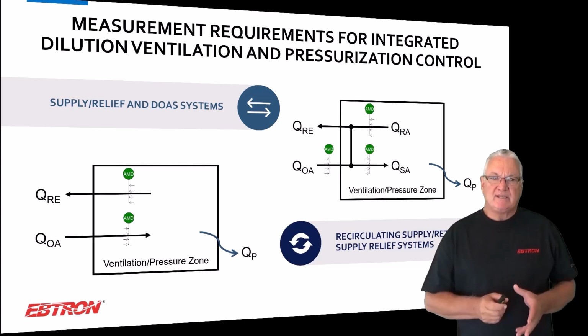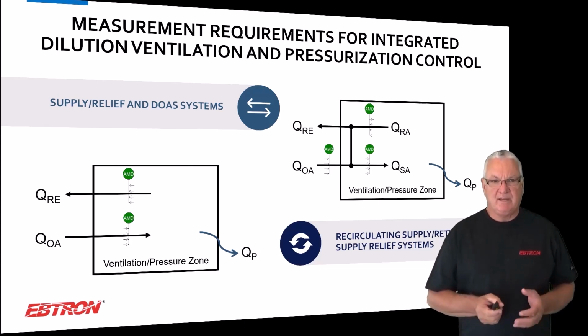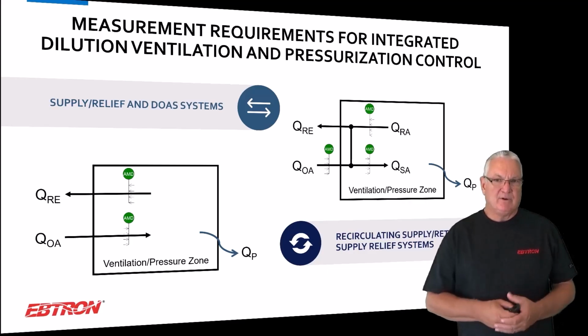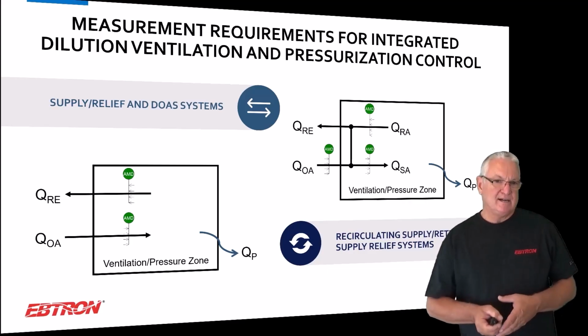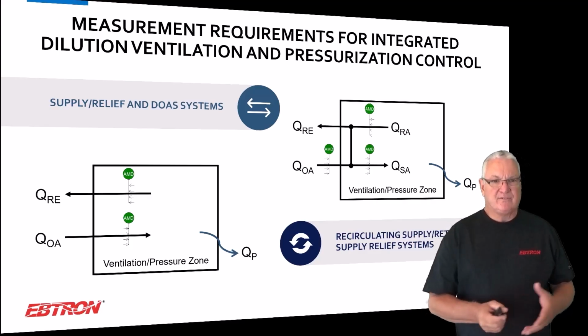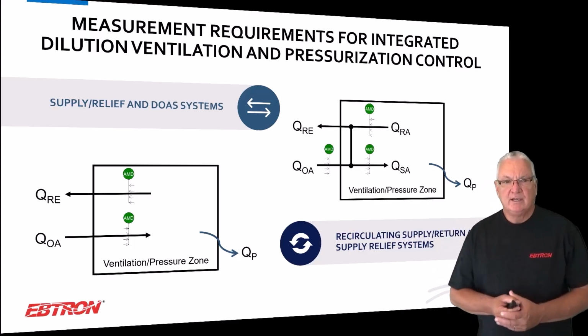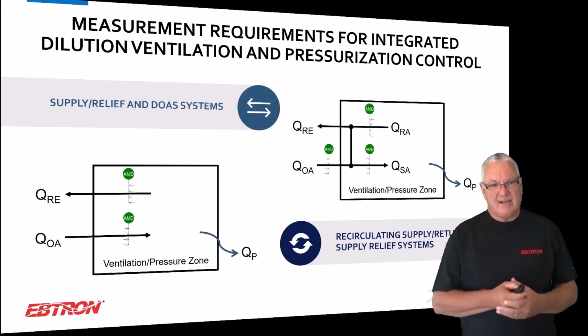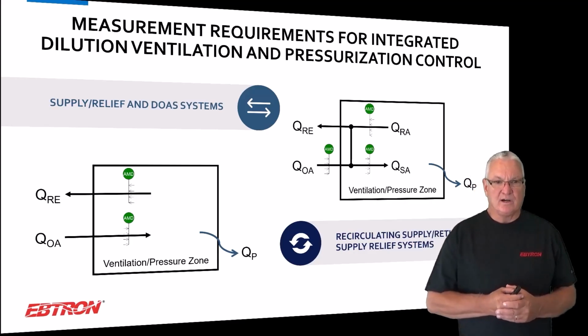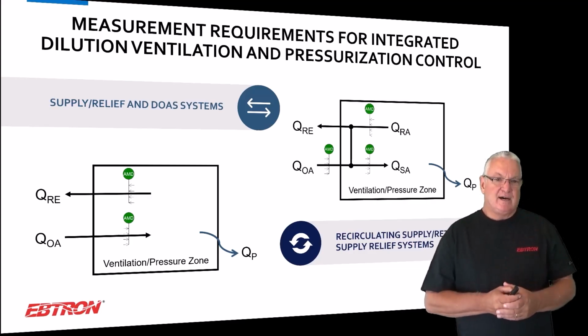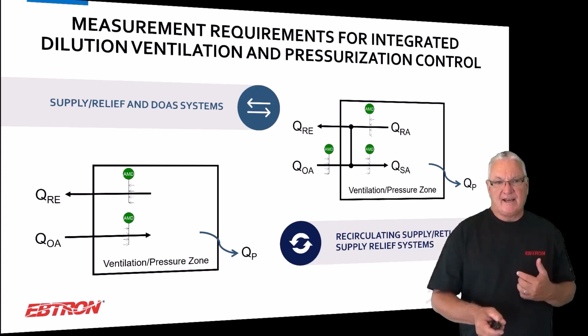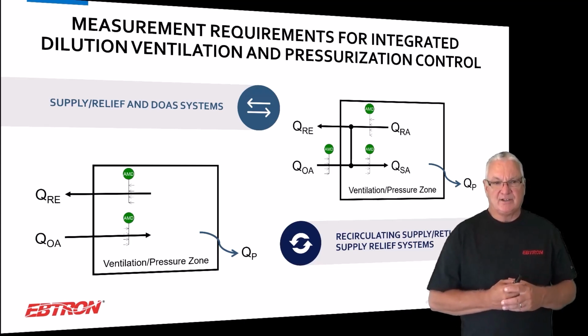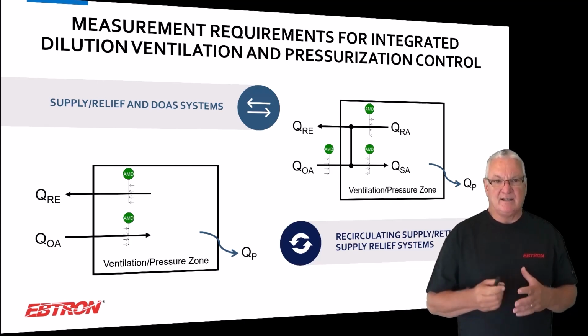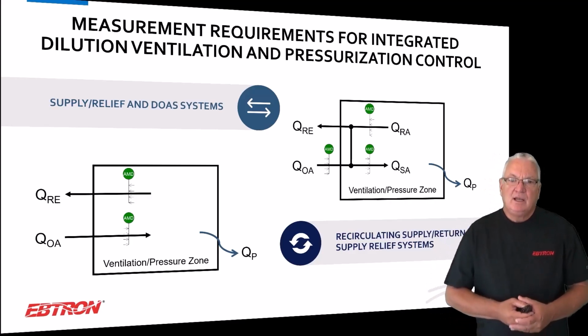And we're going to start with basically on the left there, supply relief and DOAS systems. They're pretty straightforward. I mean, you want to measure the ins and the outs. You want to find the best location you can for the total outside air, and then the best location you can for the total relief or total exhaust, whatever you want to call it. Okay, and then we're going to maintain whatever the flow rates are needed for outdoor air and whatever differential we need for pressurization. Okay, some systems might get a little more complex than that, so we may be doing the actual pressure control and the outside air at a ventilation zone. We'll kind of get into that a little bit.